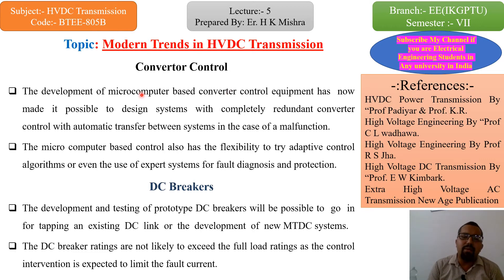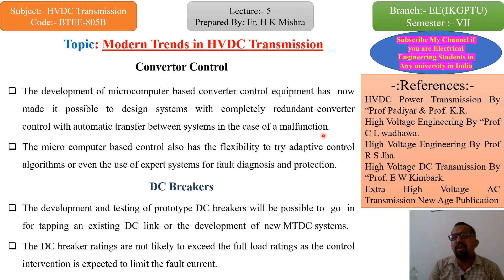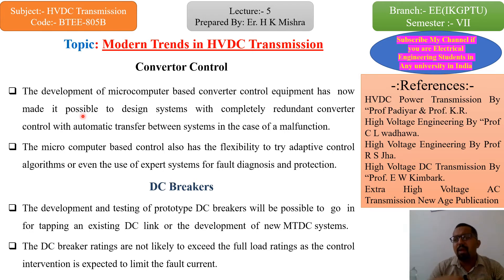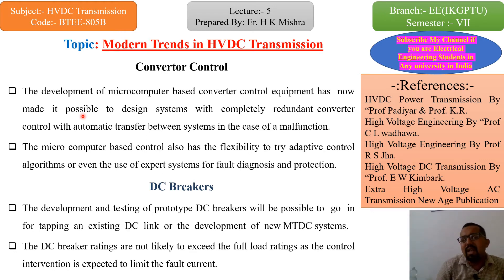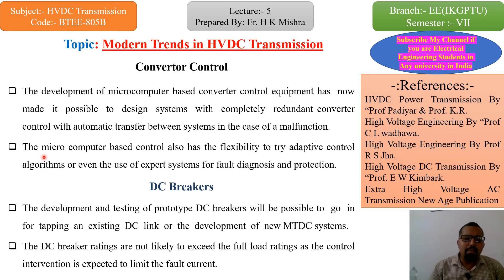Development of microcomputer-based converter control equipment has now made it possible to design systems with completely redundant converter control, with automatic transfer between systems in the case of a malfunction. The microcomputer-based control also has the flexibility to try adaptive control algorithms or even the use of expert systems for fault diagnosis and protection.